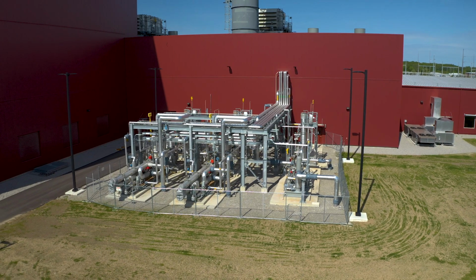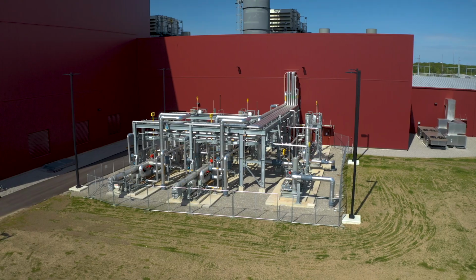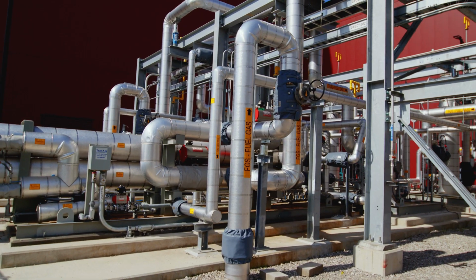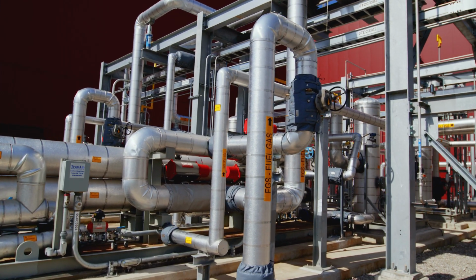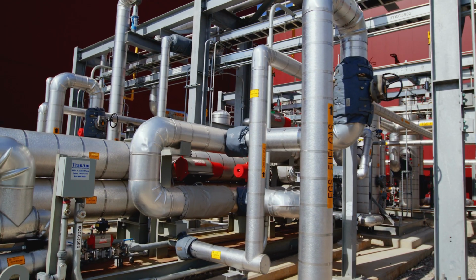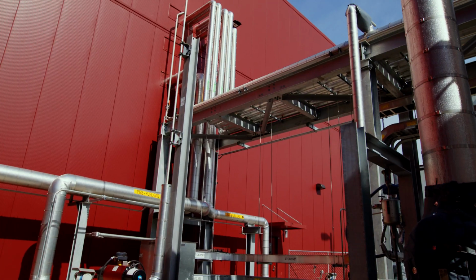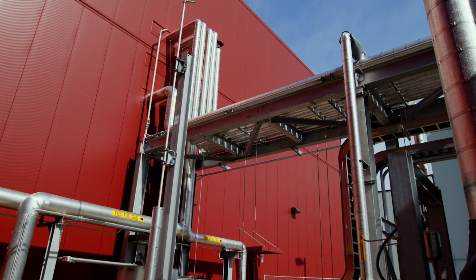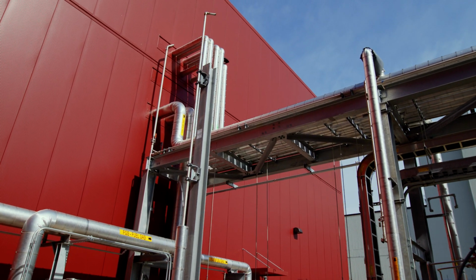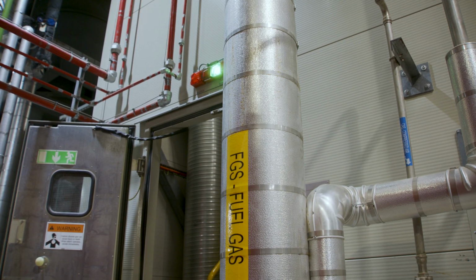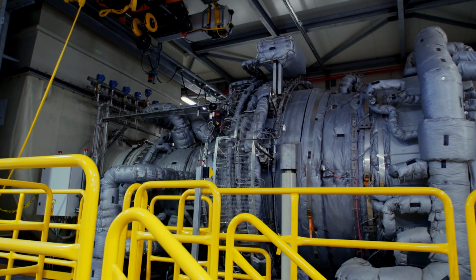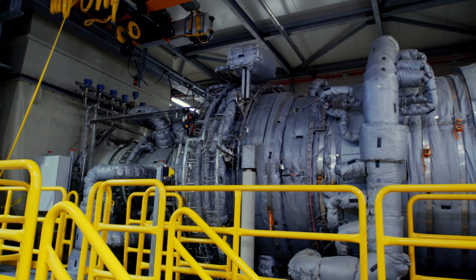Gas continues to DEP's gas conditioning area. Here, the gas for 2 of the units is heated to 484 degrees Fahrenheit. While all 3 turbines can run off the non-heated gas as needed, heating improves efficiency. Gas then flows into the combustion gas turbines. Here, the big reactions happen that generate power for the grid.